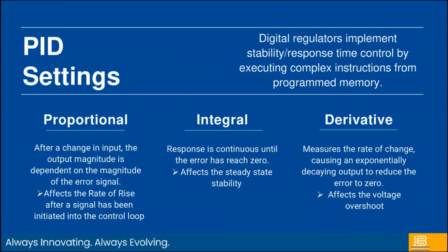Proportional gain, I'm going to describe in the terms that I like to describe it. Proportional gain, if you think about it, is looking at the magnitude of the error signal. So I've got some gain setting and I've got so much error. If my error is very high, I'm going to multiply it times that gain setting, and that's how much output my voltage regulator is going to give to make a correction. So the further away I am from set point, the more output or the more gain I'm pushing out to drive my error to zero. As I start to drive it, I'm hopefully correcting in the right direction, so my error signal keeps getting smaller and smaller. As it gets smaller, my output gets smaller as well. So by definition, proportional gain will never drive the voltage perfect. It's always going to have some type of error because the math just works that way.